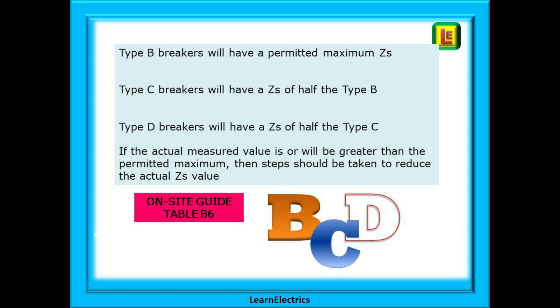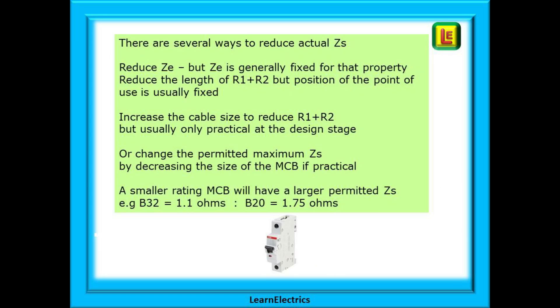If the actual measured value is or will be greater than the permitted maximum then steps should be taken to reduce the actual ZS value. Ideally we should calculate what the actual ZS would be at the design stage before we begin the installation. It is far easier to change circuit parameters before they are built and this is less costly too. There are several ways to reduce the actual ZS. Reduce ZE but ZE is generally fixed for that property. Reduce the length of R1 plus R2 but the position of the point of use is usually fixed. Increase the cable size to reduce R1 plus R2 but usually only practical at the design stage. Or change the permitted maximum ZS. A smaller rating circuit breaker will have a larger permitted ZS. For example B32 is 1.1 ohms but a B20 is 1.75 ohms.